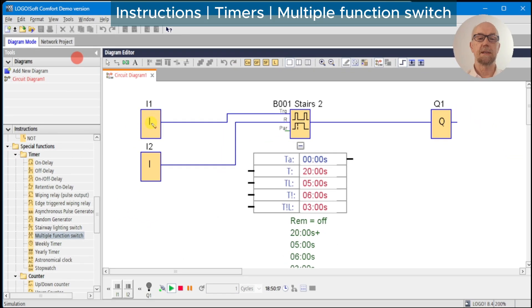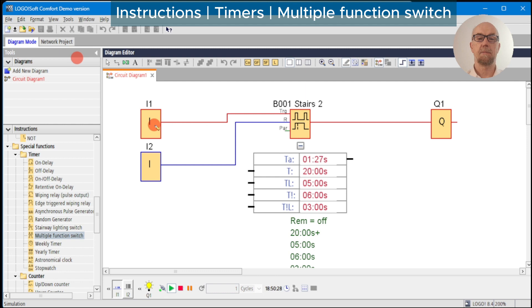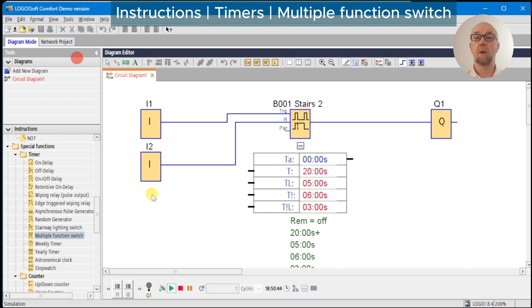Of course at any stage we can override with the reset. Finally, if we toggle the input and hold it on for five seconds, the lamp now remains on indefinitely. To clear the lamp we can just hit the input switch again — touch and the light goes off. This is a useful feature where you want an override, maybe for maintenance, to leave all the lights on in the stairwell.